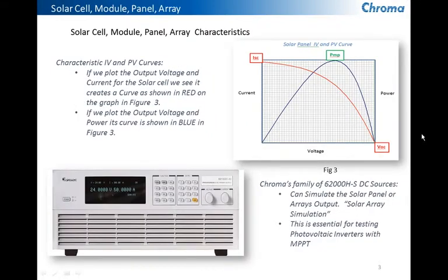When you look at this graph that I'm showing here, the red line shows what we refer to as the IV curve. It starts all the way up at the maximum current which would be an absolute short circuit of the solar panel's output and that would be referred to as short circuit current. With no load applied to the solar panel it produces an open circuit voltage and these two points create this curve based on an algorithm created by Sandia and by European EN 50530 standards.